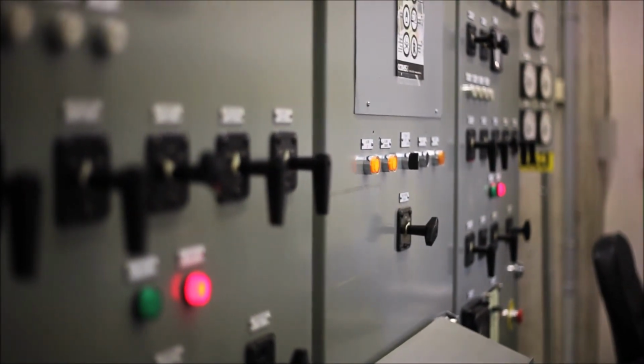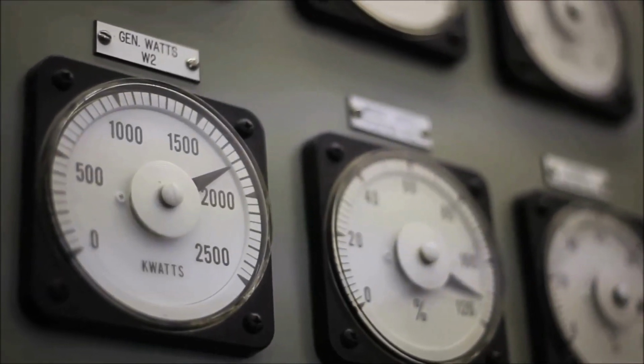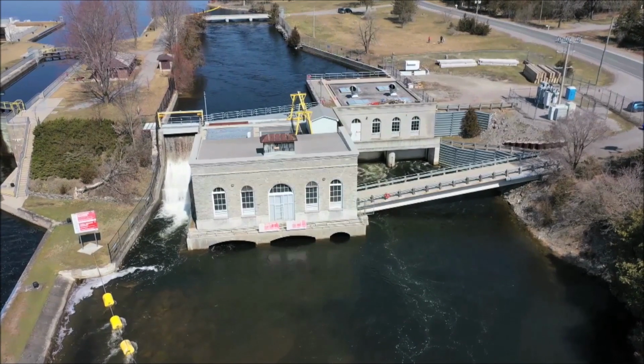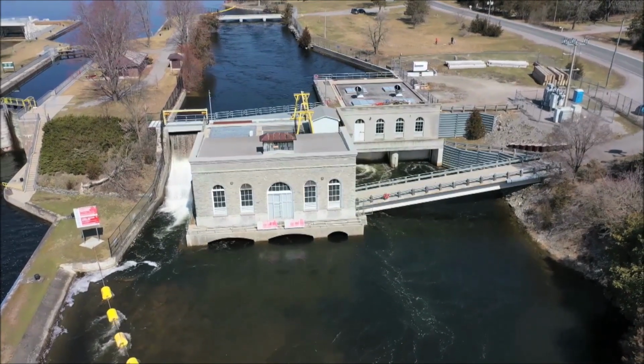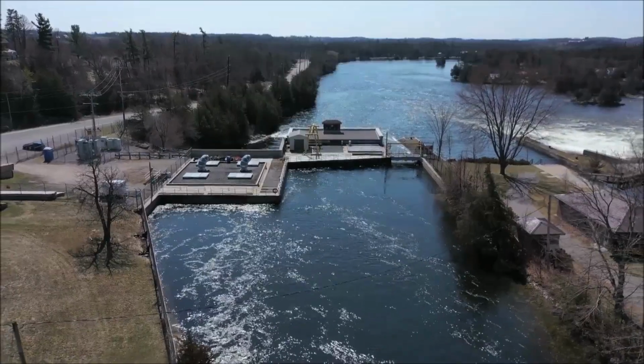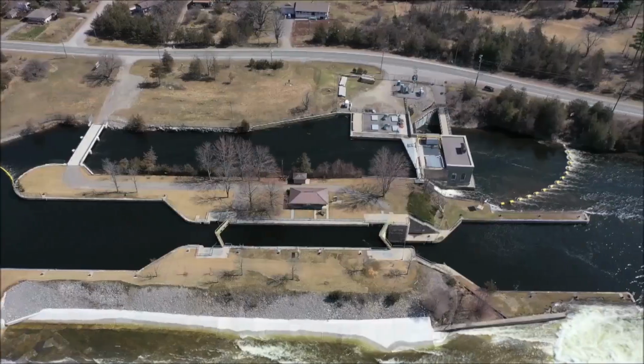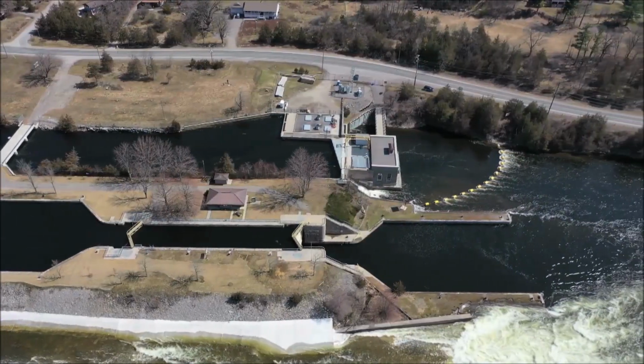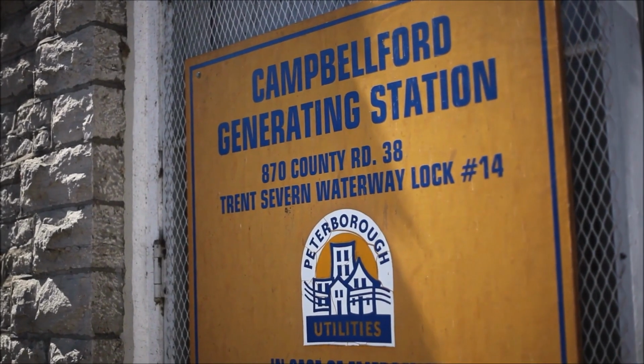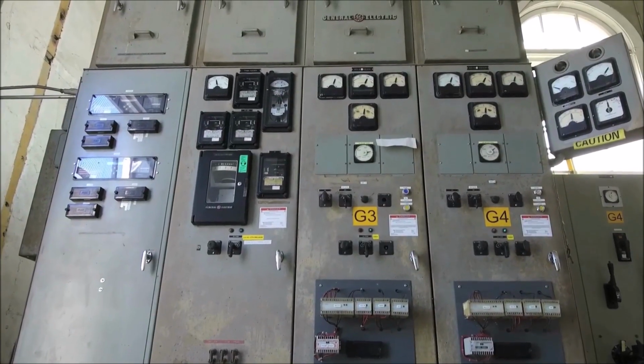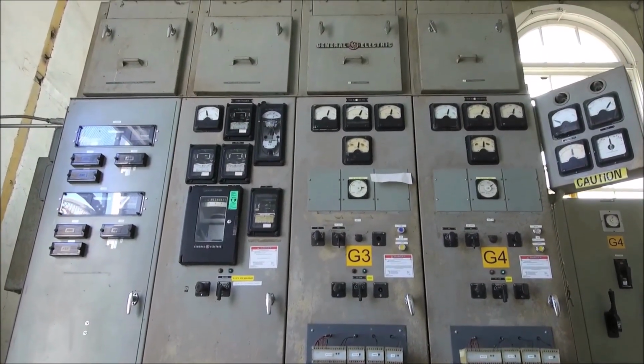We currently have a PLC system in Plant 2 for the remote monitoring SCADA operations. Although the system has been here for many years, our primary method for remote access was through the HMIs. We have since connected Plant 2 directly and are looking to replace the PLC system to provide greater control, alarms, and monitoring. We currently still connect to the HMI in Plant 1, but this will also be updated when the new PLCs are installed.